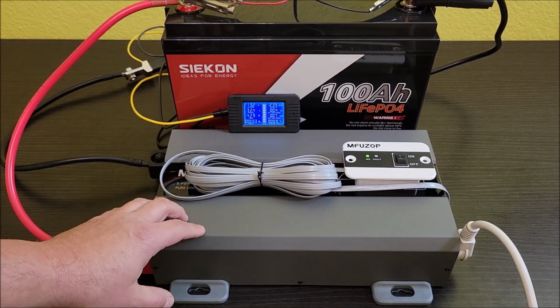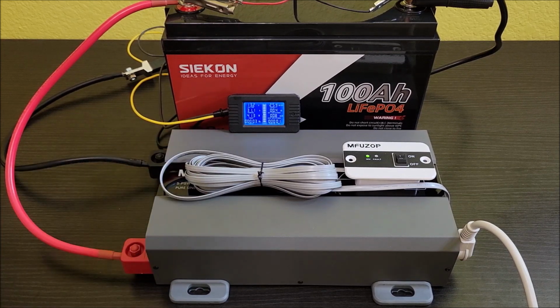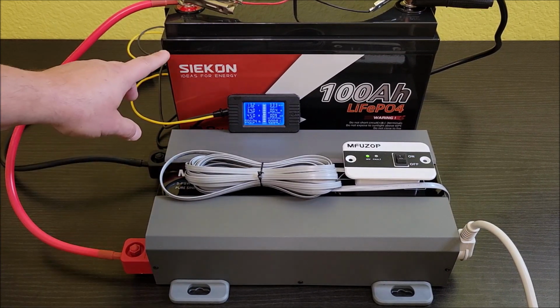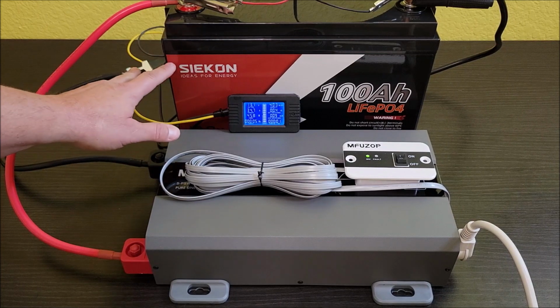400 watts is not something that's stressing this inverter, so it's going to drop back down. But right now we're at about 430 watts, which is putting about a 35 amp load on this battery, which is nowhere near its peak or its continuous.